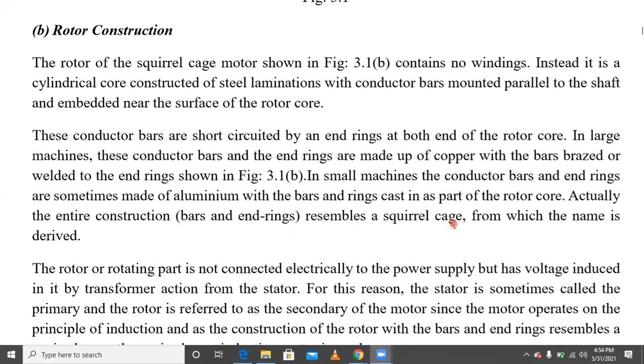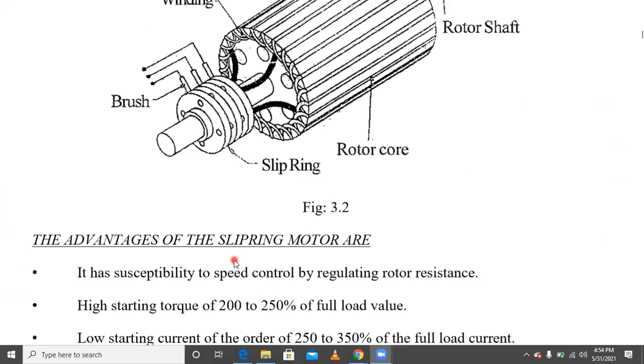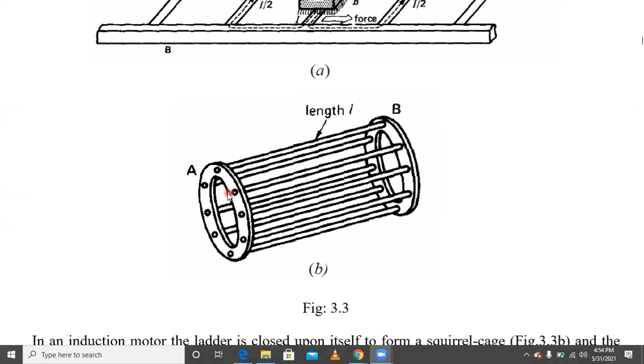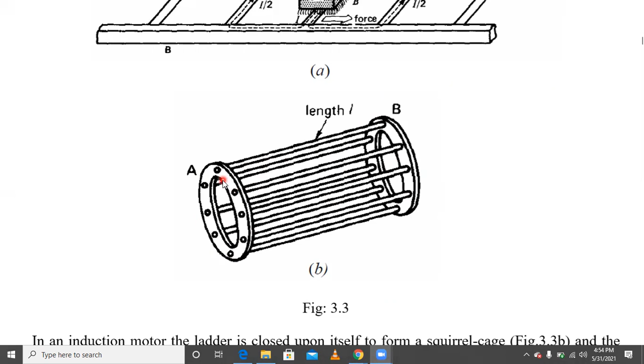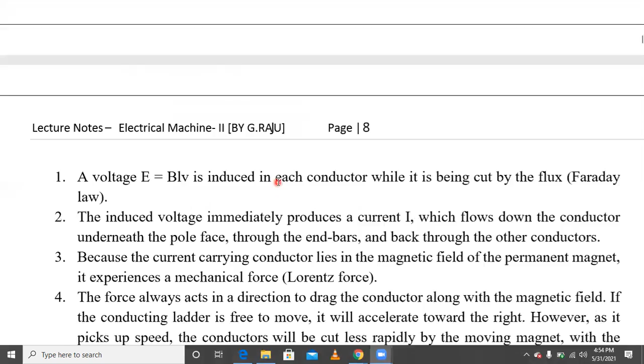For small machines, the conducting bars and end rings are made by aluminum; that's the difference. The bars and rings are cast as part of the rotor core, and the entire construction resembles a squirrel cage, from which the name is derived. These are the different conducting bars, not a winding, just bars placed like this, short circuited by end rings A and B, parallel to the shaft. For large machines, the conducting bars and end rings are made by copper; for small machines, they are made by aluminum.